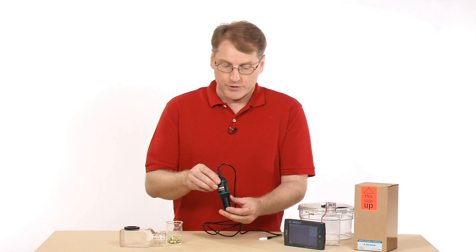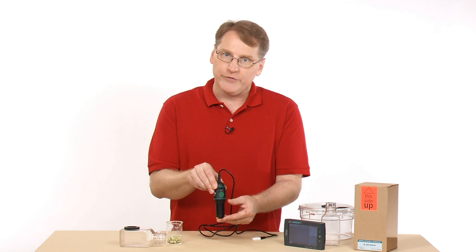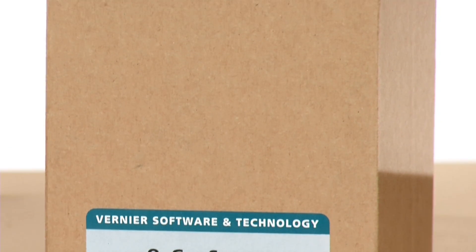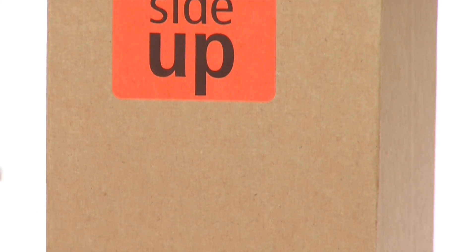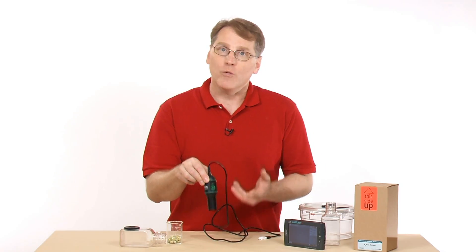One thing about this sensor is that you need to store it vertically. It comes in this box that says this side up, and the sensor is in the box in that orientation. And it's important that you do store it that way.